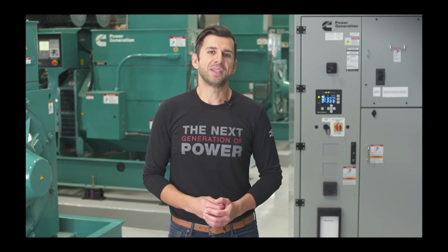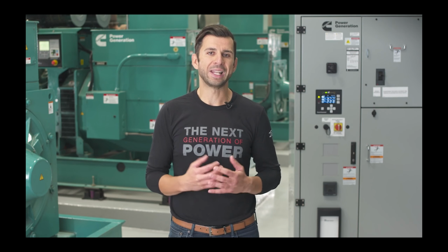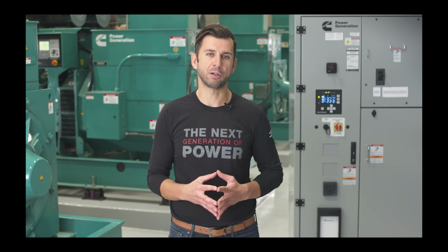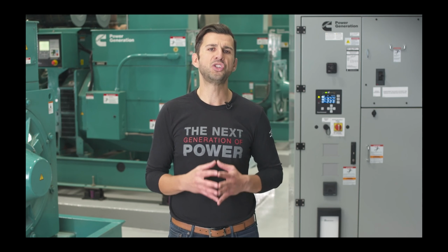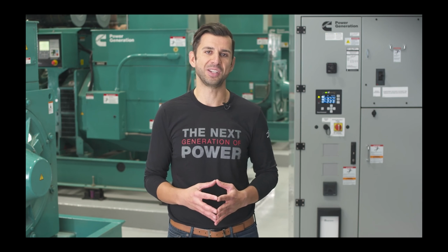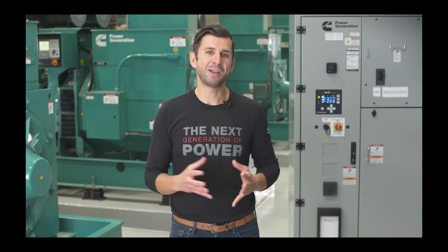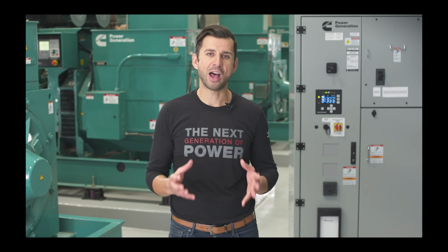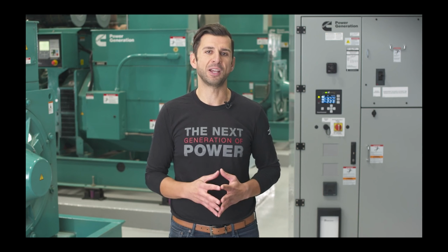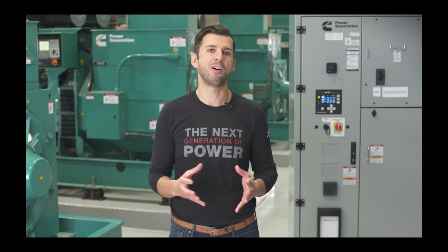The transfer switches have a short time rating which allows them to withstand a high fault current for up to half a second, which enables selective coordination strategies. For a facility manager or an operator, this means costly repairs or inconvenient downtime can be minimized after a fault. But we didn't stop there with the innovations.